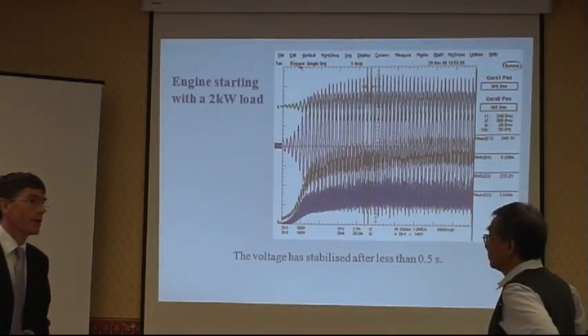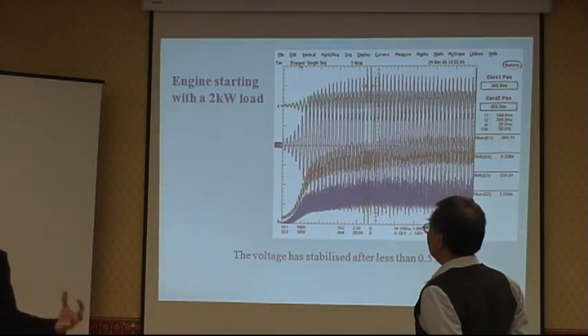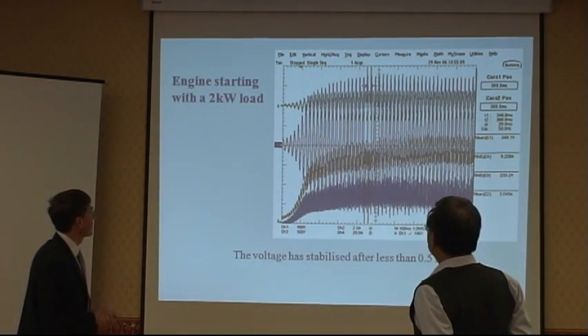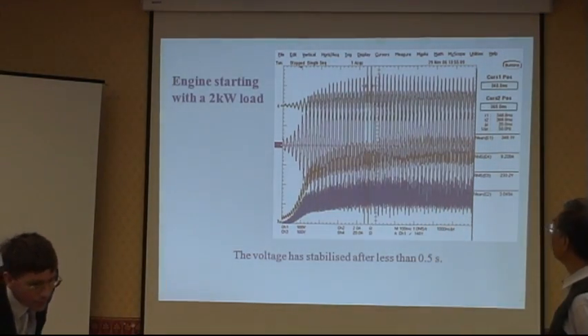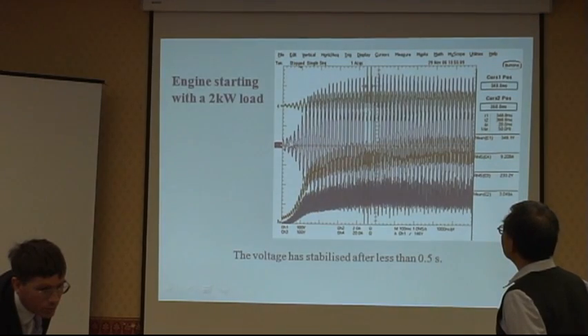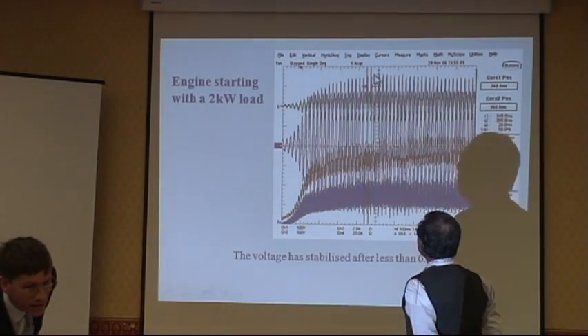So this is the waveform you get if you start the engine with the full load connected. So 2 kilowatts is already connected when you start the engine. 这是在有负载之下启动引擎，马上发电出来的波形。We can see the load current increasing in green. And the output voltage increasing, but still stabilizes and maintains 233 volts with the full load.